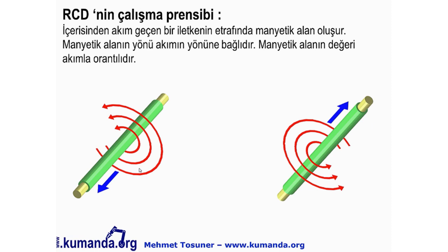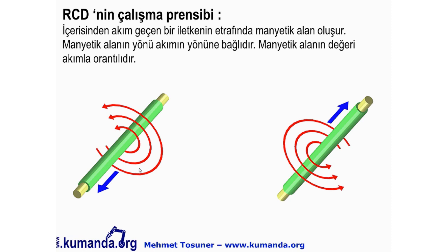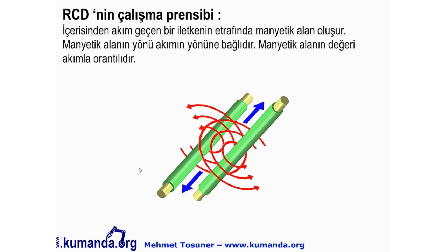RCD'nin çalışma prensibi: içerisinden akım geçen bir iletkenin etrafında manyetik alan oluşur; manyetik alanın yönü akım yönüne, değeri ise akımla orantılıdır. Birbirine ters yönde akım geçirilen iki iletkenin manyetik alanları yan yana getirildiğinde birbirini yok eder — bileşke manyetik alan sıfır olur. RCD'nin çalışma prensibi de budur.